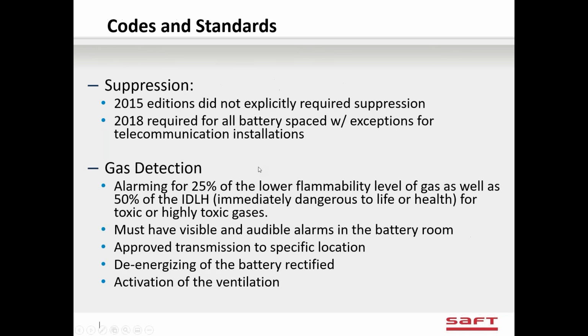I should say lithium-ion batteries do not gas in normal operation. They only let gas out of the cell in a venting or thermal runaway situation. So if the cell gets very hot and the pressure builds up inside it, it will vent the electrolyte out into the air. That's the venting that we're talking about. Normal operation, there's no venting at all because it's a completely sealed battery.